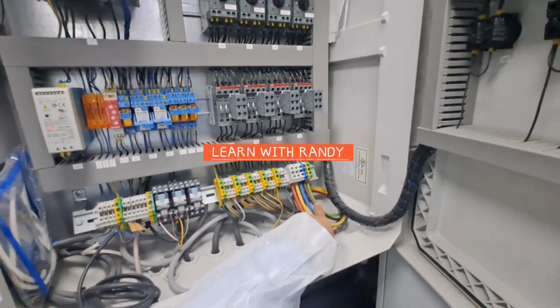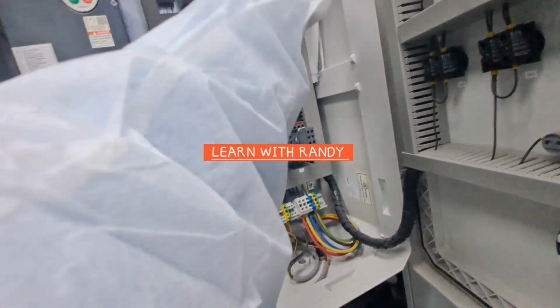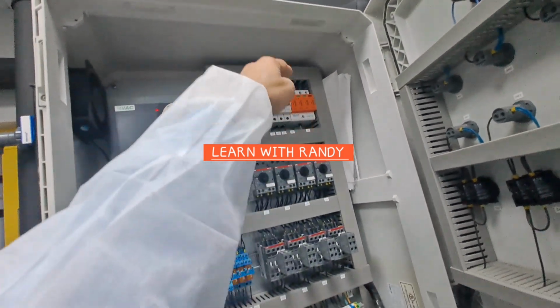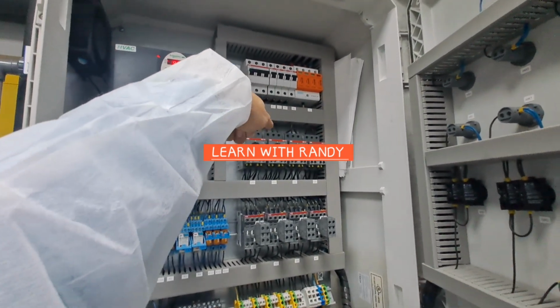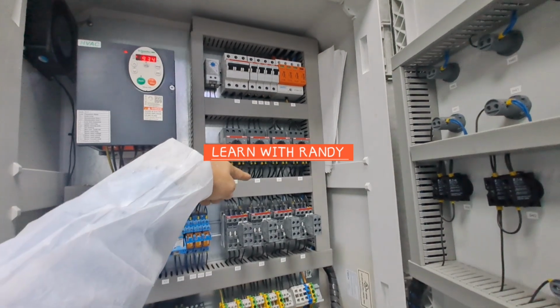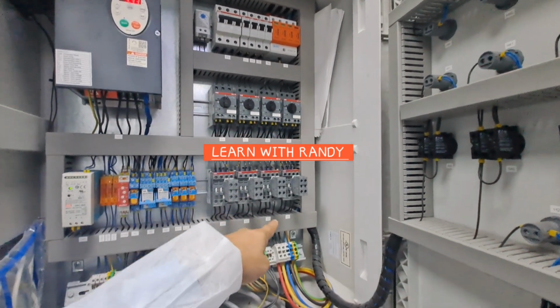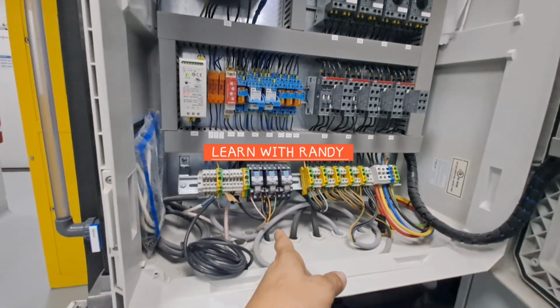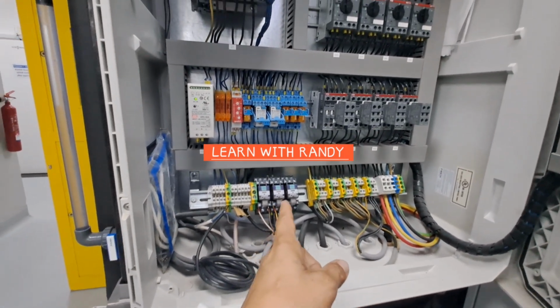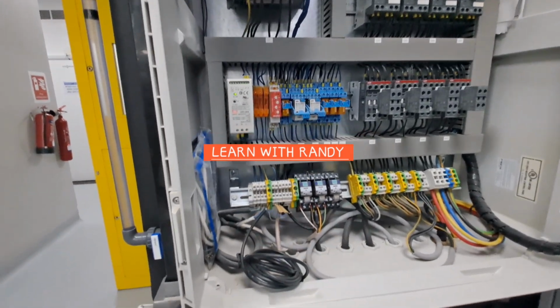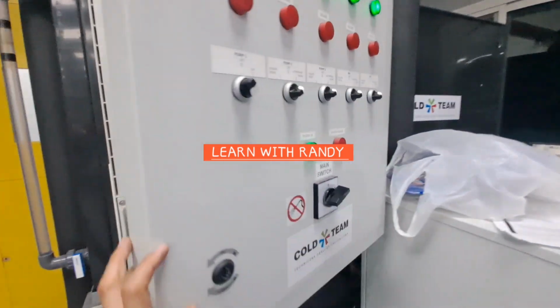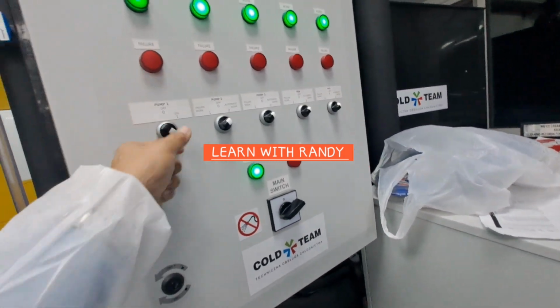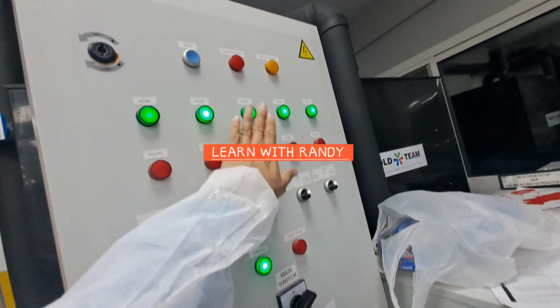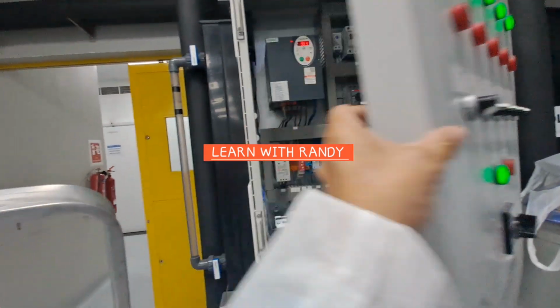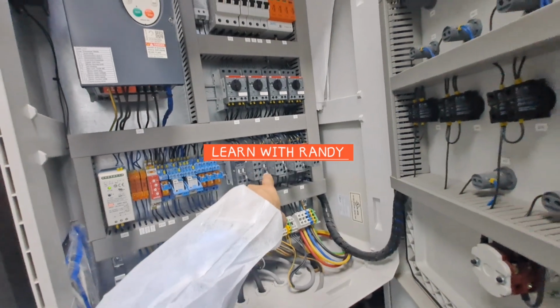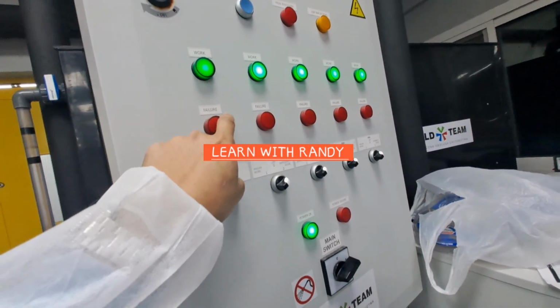Okay, so what we have here is the supply incomer, and it will go to these circuit breakers, then feed to the contactors, and then to the load. These are the micro relays for the input and output of the controller, and these are all the switches. This is the main cut-off switch and the selector switch to turn on and off. These are all the indicators. If there is a failure, the auxiliary contact of this contactor will give a signal to the failure indicator.